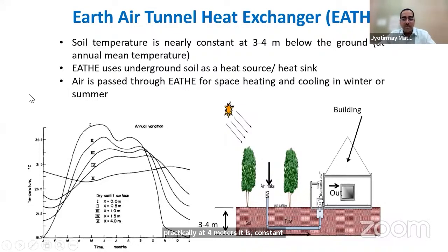If your ambient is cooler than this ground temperature, you can use it for heating air, and if your ambient is warmer, you can use it for cooling. This temperature can be calculated as a thumb rule: if your annual maximum temperature is, say, 47 degrees—as in Jaipur, where I come from—and your annual minimum is, say, 3 degrees, you calculate the mathematical average, which comes out to 25. I dig a hole and measure the temperature 4 meters down the ground.